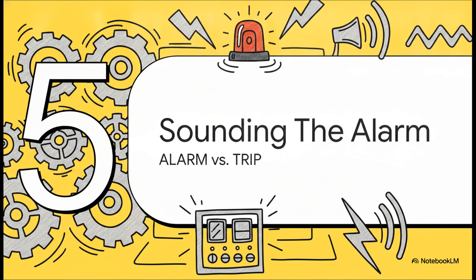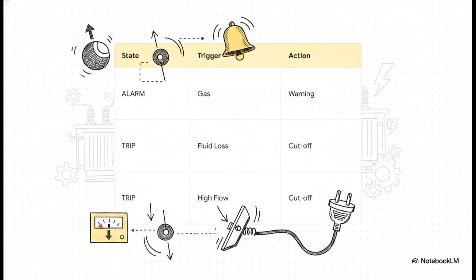Which brings us to Section 5, sounding the alarm. Alarm versus trip. So there are two completely distinct escalation protocols here. A slow gas buildup that drops the upper float triggers a simple alarm. It's kind of like a heads-up, something is wrong signal. But if you have severe fluid loss dropping the lower float, or a massive pressure surge swinging that flap valve, the relay triggers an immediate, mandatory trip. This is a hard cutoff signal that steps in to shut the entire transformer down.